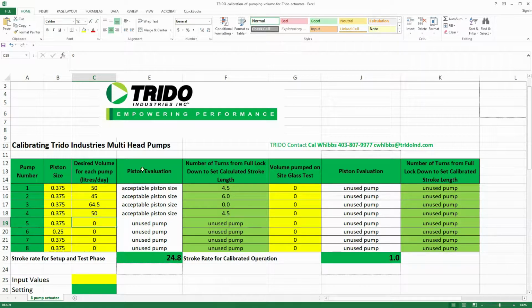Once you have columns B and C filled out, the adjustments required for each pump are calculated and shown in column F. There will always be one chemical pump adjustment at 0. Record the number of turns for each pump and the stroke rate number. In this example, it's 24.8.